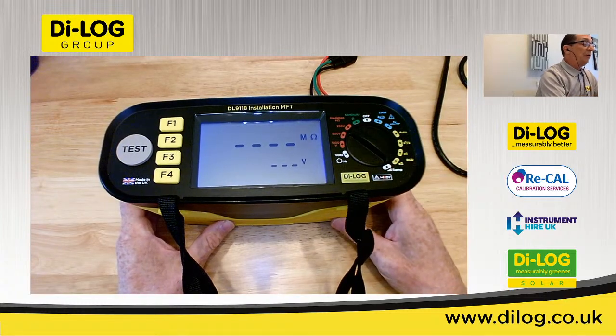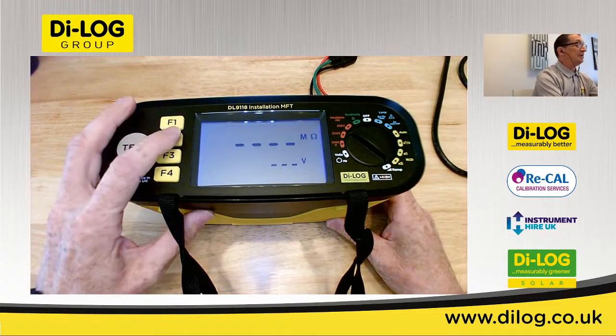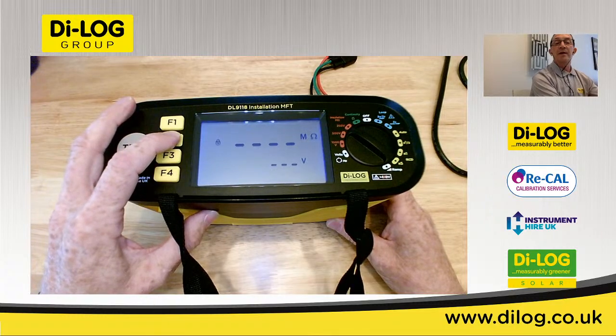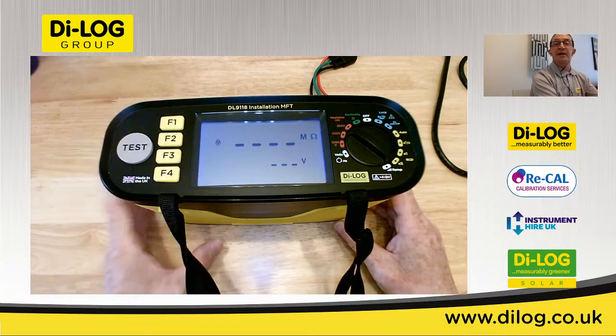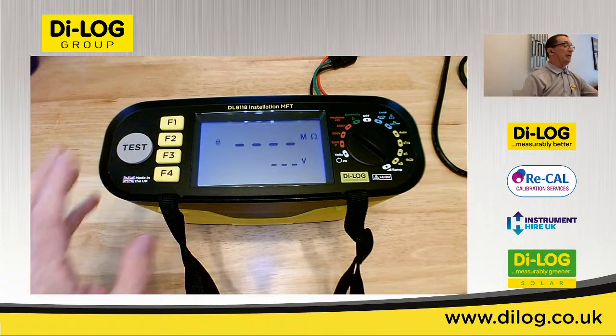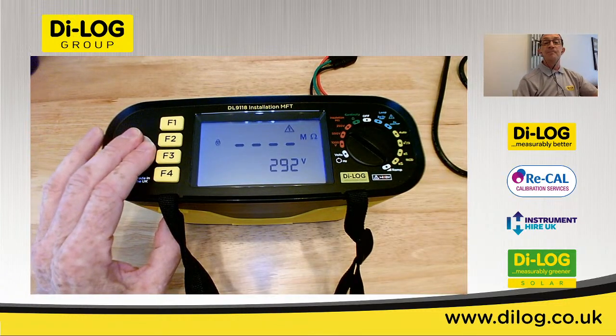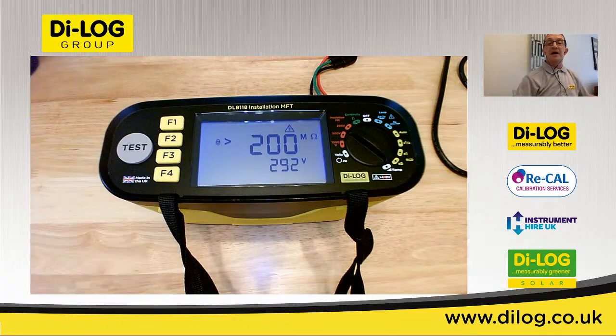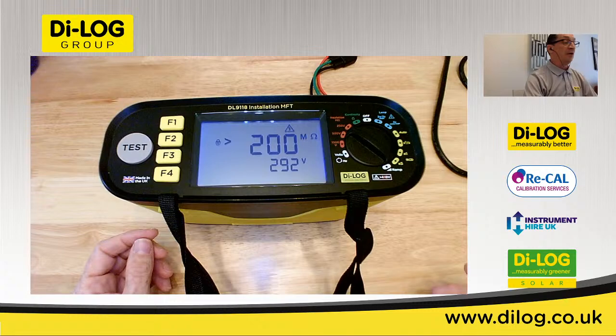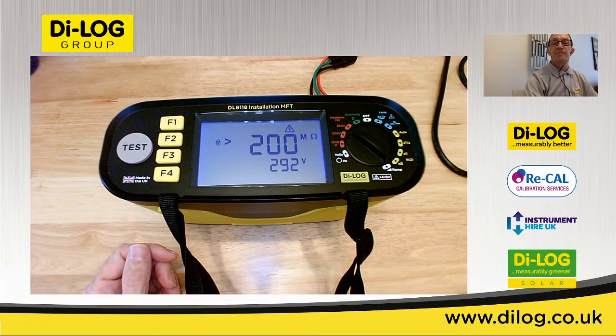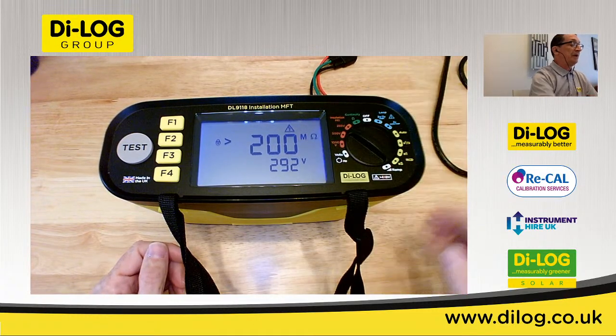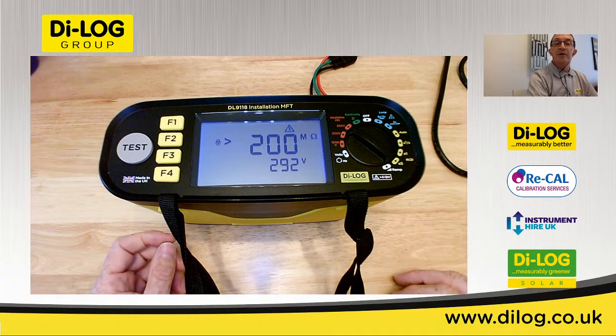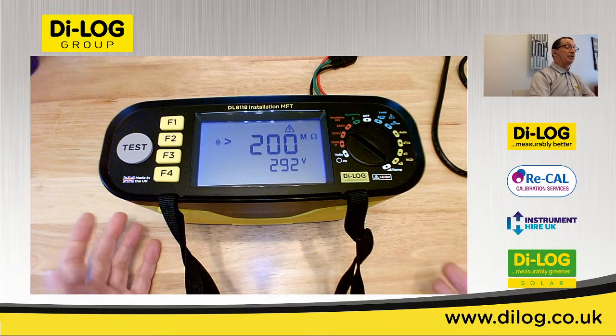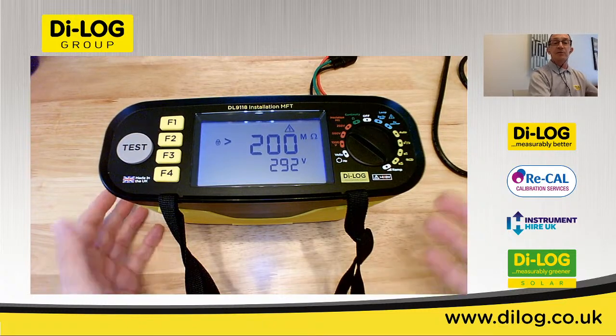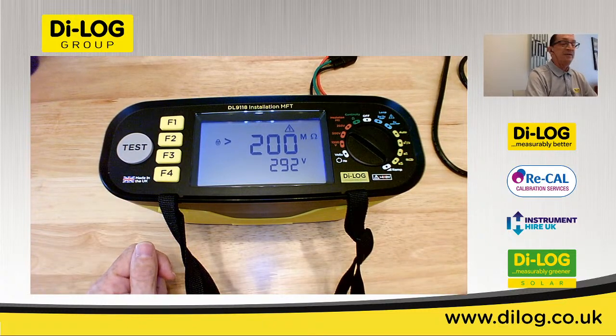Another nice feature on the insulation test is on function 2, where the little lock symbol appears on the display, and that means that the test button can be latched. So if I begin a test now, that's now latched and is constant until I press the test button again to end the test, or I turn the rotary dial off. We can see we've got our insulation reading and we've also got our output voltage. So we get an indication as to whether the instrument is kicking out the voltage that it should do to carry out the insulation test effectively.